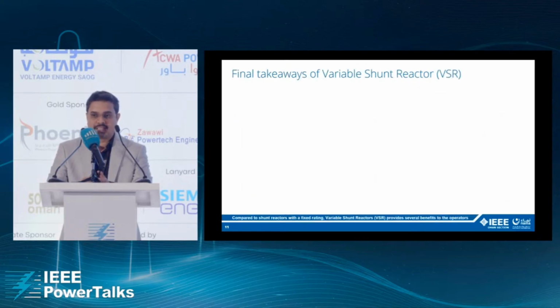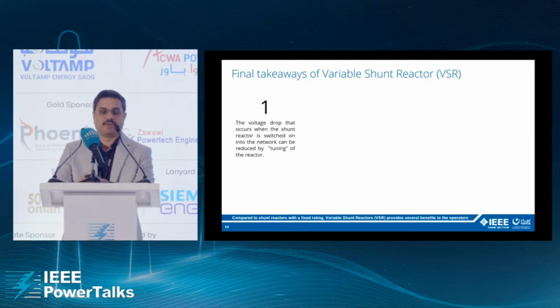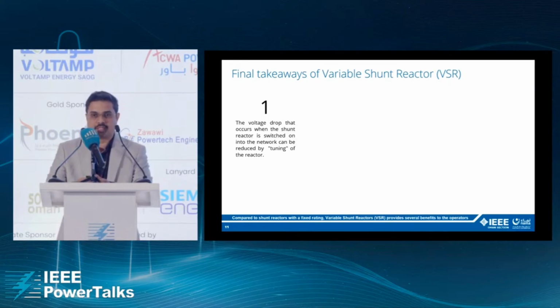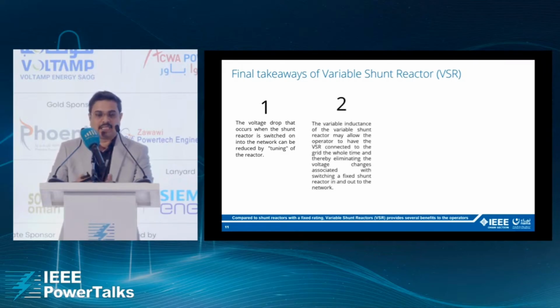So the final takeaways: whenever you need a dynamic absorption of reactive power from the power system, it can be done by using a shunt reactor equipped with the OLTC, which can fine tune the number of turns. It can simply keep on absorbing depending upon the load, the reactive power generated, and whatever reactive power is being consumed by the dynamically varying load. Then, the variable shunt reactor is connected at all times to the system, with no need to disconnect it and create any turbulence. And this is very important when you have large scale integration of renewables.